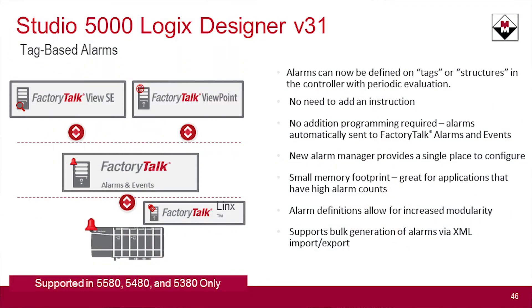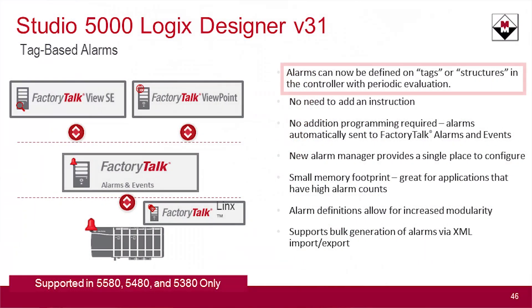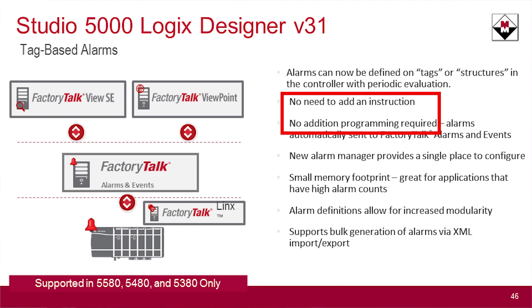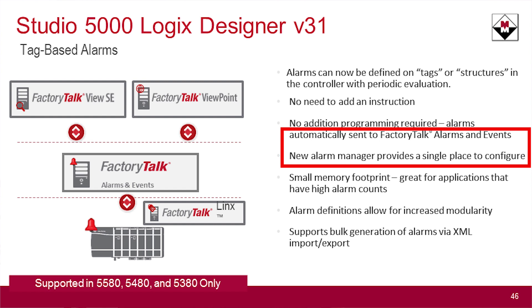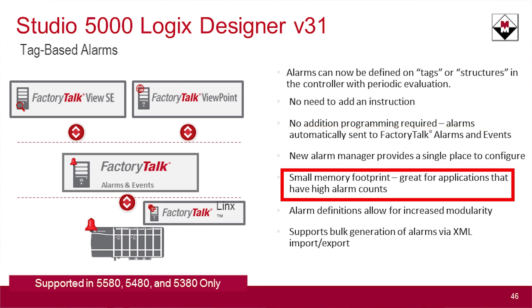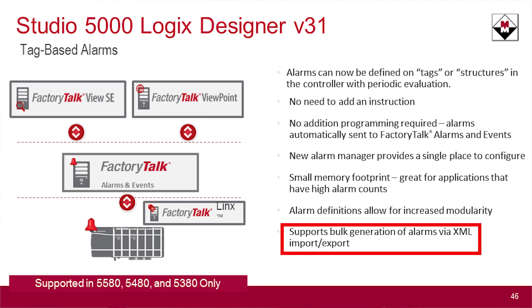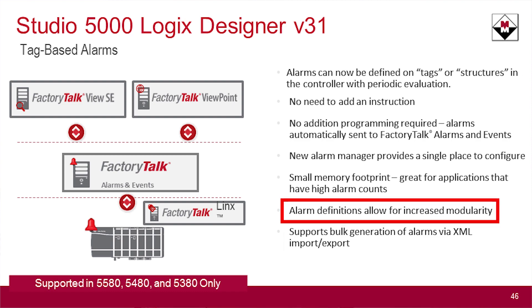Version 31 also introduces a new type of alarm: tag-based alarms. No longer do you need to write an instruction to create it. The instruction was nice but took up a lot of memory, and with a large application with many alarms you'd often need a larger controller just to handle them. Now it's a checkbox in the tag editor — you manage it all there, there's no programming to write. It's delivered as part of the FactoryTalk Alarms and Events server, with a small memory footprint. You can also do bulk alarm generation, export to XML, create them there, and import them back in. It also supports modularity — add-on instructions can have those alarms embedded very easily.